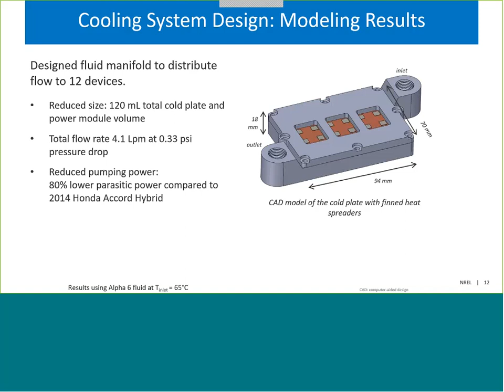And so this slide describes the flow path within the cold plate. We're using a parallel flow configuration that's shown by the blue line there. The fluid comes into the inlet, and then it flows through a manifold, and then it's distributed to the 12 jets that are directly below each device. The spent fluid then exits out the opposite end.